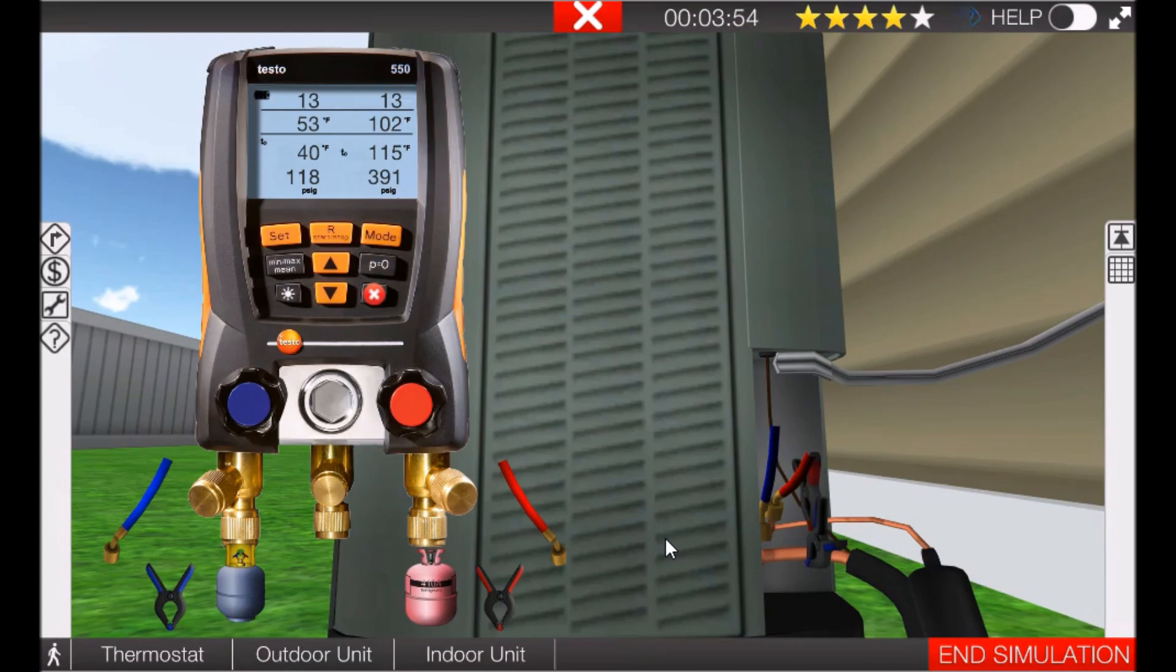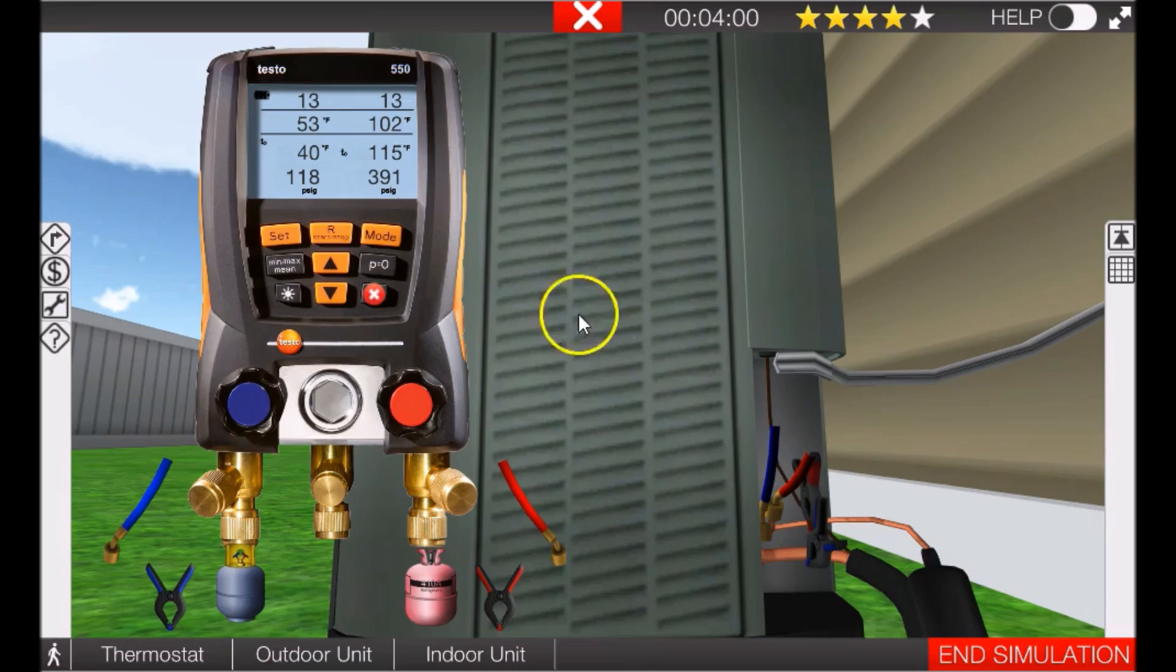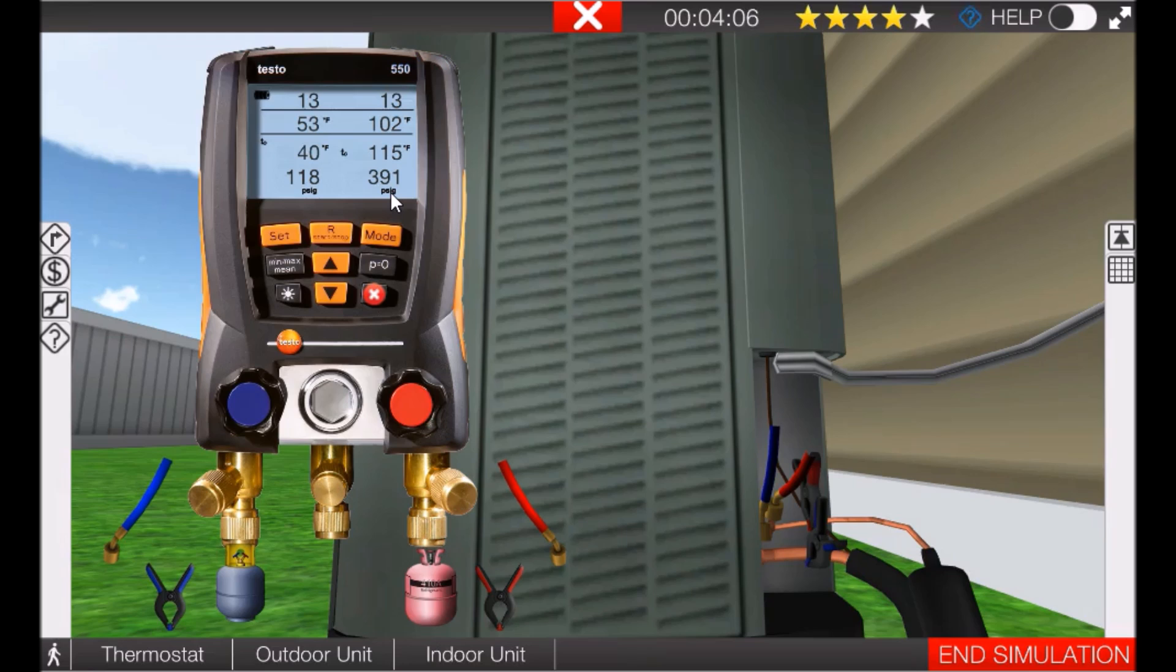Okay, so now let's take a look at what's going on. If you remember, we had 351 psig on the high side - now we have 391. The reason the pressure has gone up on the high side is because we are now able to extract more heat from the indoor air now that the new filter's in there.